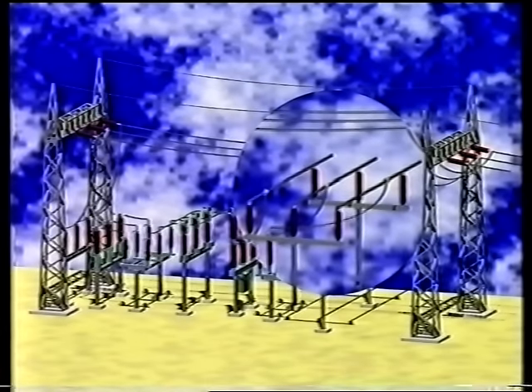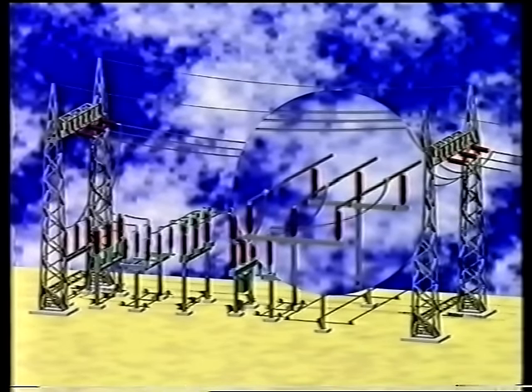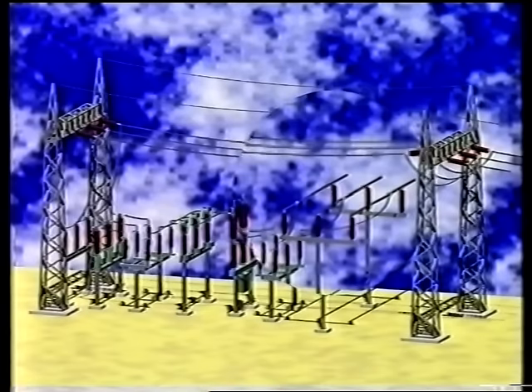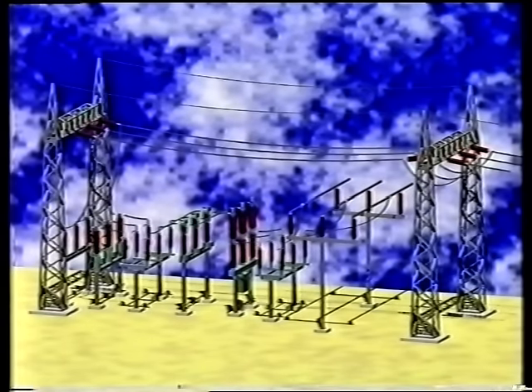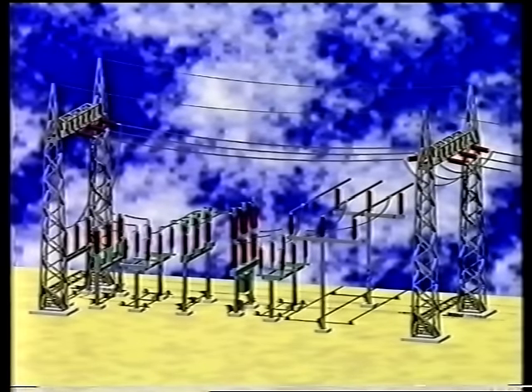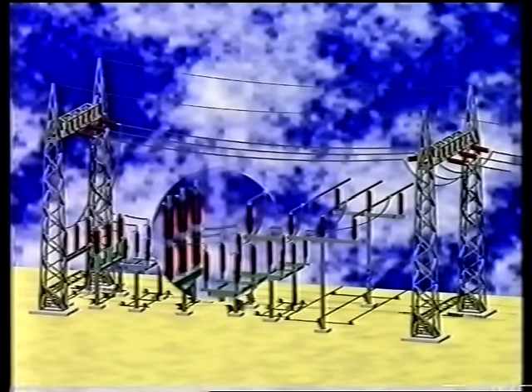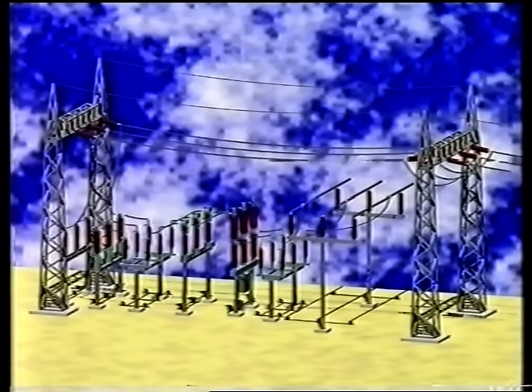Rigid conductors in high-voltage switchgear are, as a rule, made by tubes. As long as they are in a straight line, they may be calculated by IEC 60865. This is also possible with horizontal cable connections between components, or strained connections between steel structures.